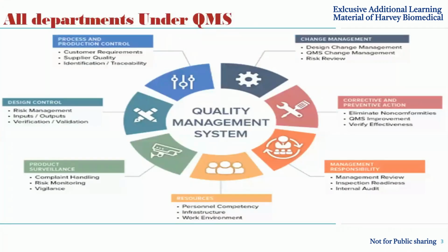As Vivek asked, all the departments fall under the quality management system. Only if the combination of all departments makes your facility a quality management system facility can they give the approval that your facility falls under ISO 13485:2016, and you can go ahead with the manufacturing of the medical device.